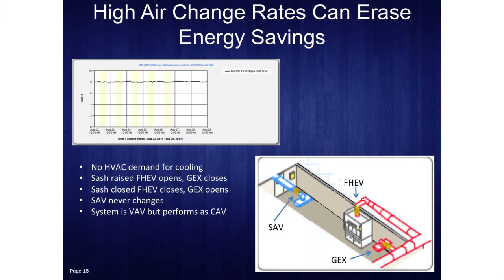So understanding these systems a step beyond just saying, I have a VAV system and close your sash, really starts to change how much energy savings and how much actual impact you have. And you can find these kinds of examples throughout our talk, whether it's exhaust stack discharge velocity, where you're talking about closing the bypass because of your roof, or reheat. All these different things are making sure that your dynamic system is actually dynamic.